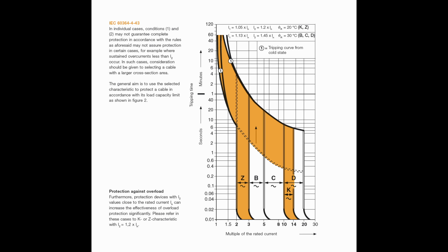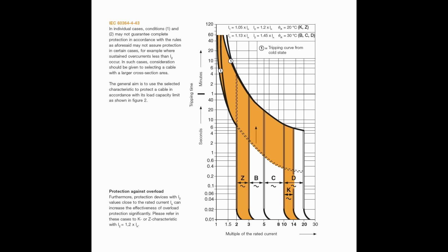So for any particular rating of circuit breaker, along the bottom here is the multiple of it. So if I had a 6 amp circuit breaker, you can see there that the type C would be tripping somewhere between 5 times, which would be 30 amps, and 10 times, which would be 60. So pretty much what we saw previously.